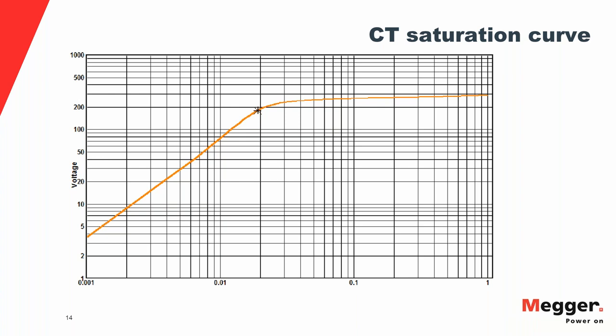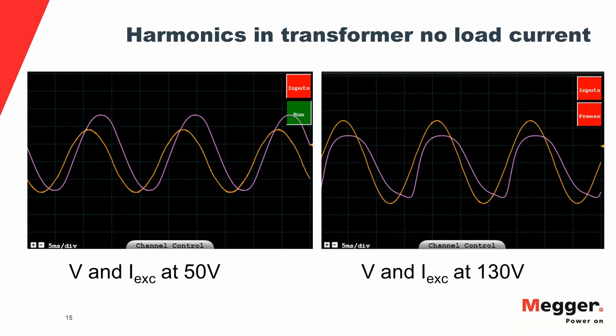This can be highlighted using a CT saturation curve. On the Y-axis is the voltage applied across the secondary winding; on the X-axis is the excitation current. There is a saturation point marked — at 180 volts, indicating a C200 CT. Taking two points on the curve — at 50 volts and at 130 volts — and observing the waveforms: at 50 volts the current (shown in purple) is a clean sinusoid, while at 130 volts there is significant distortion in the current waveform.